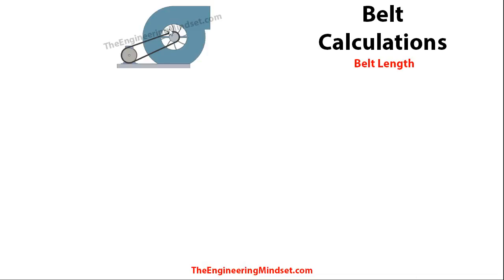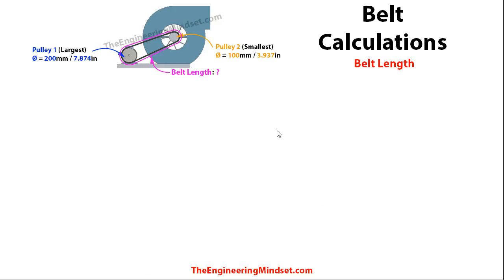First of all we'll look at the belt length — what length does this belt need to be? In this example we're looking at the belt between the induction motor and a centrifugal fan in an AHU. We already know the size of each pulley, either from manufacturer's data or by measuring on site. Pulley one is always the largest pulley, and we also know the center distance between the two pulleys.